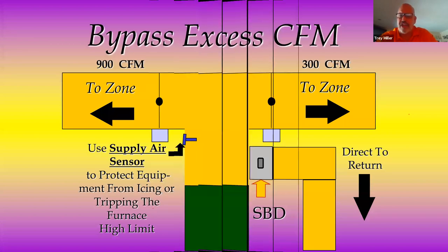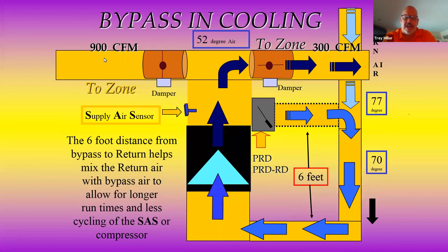Now, let's look at it in cooling. The nice thing about cooling, every night I go to bed, I'm going to cut the living area off. I'm just diverting the BTUs to the sleeping area. And all that CFM and capacity that was going to the living area, I will bypass, mixing it with my return air, right back across the coil. As I do this, I'm going to drop the temperature of the coil. If I drop the temperature of the coil, I will also drop my discharge. And gentlemen, if I drop my discharge, then I reduce the runtime on the condenser outside. This is a win-win scenario for everybody. It keeps the system running less.